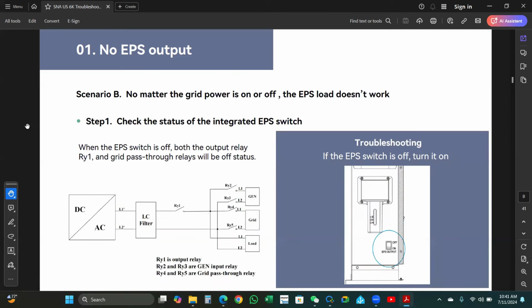No EPS output, scenario B. No matter whether the grid power is on or off, the EPS load doesn't work. Step one, check the status of the integrated EPS switch, which is on the left side of the inverter, which is this side. When the EPS switch is off, both of the output relay RY1 and the grid pass-through relay will be off.